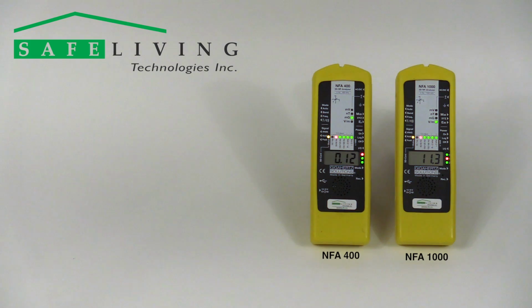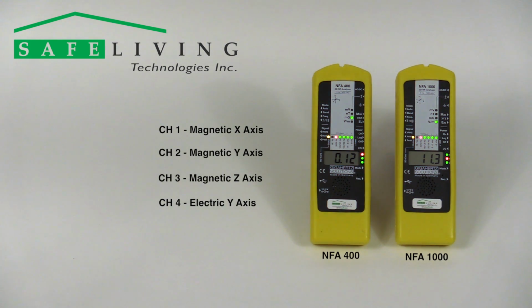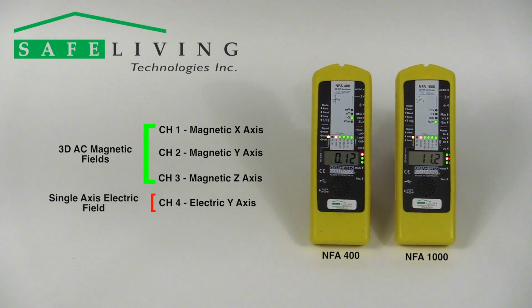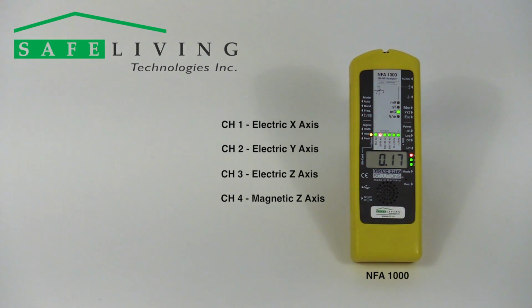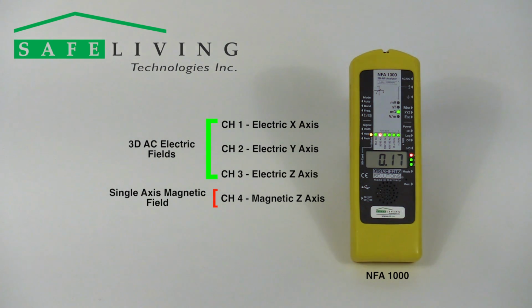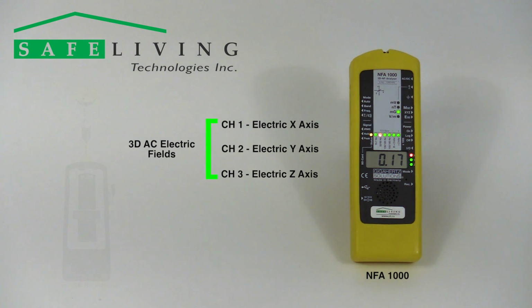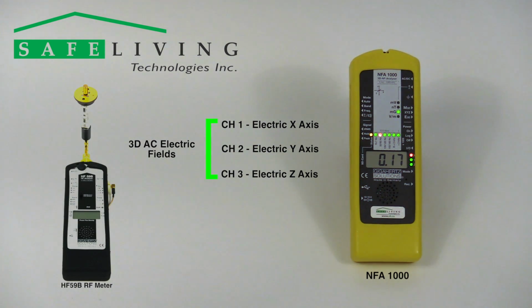The NFA1000 and NFA400 log 4 channels of data at the same time. In other words, if you are logging 3D AC magnetic fields, the meter will also log single-axis electric field measurements. And using the NFA1000, if you are logging 3D AC electric field measurements, the meter will also log single-axis magnetic field values. If you have an external device, such as an HF59B connected to the AC-DC input, the data from this device will automatically be recorded on the fourth channel.